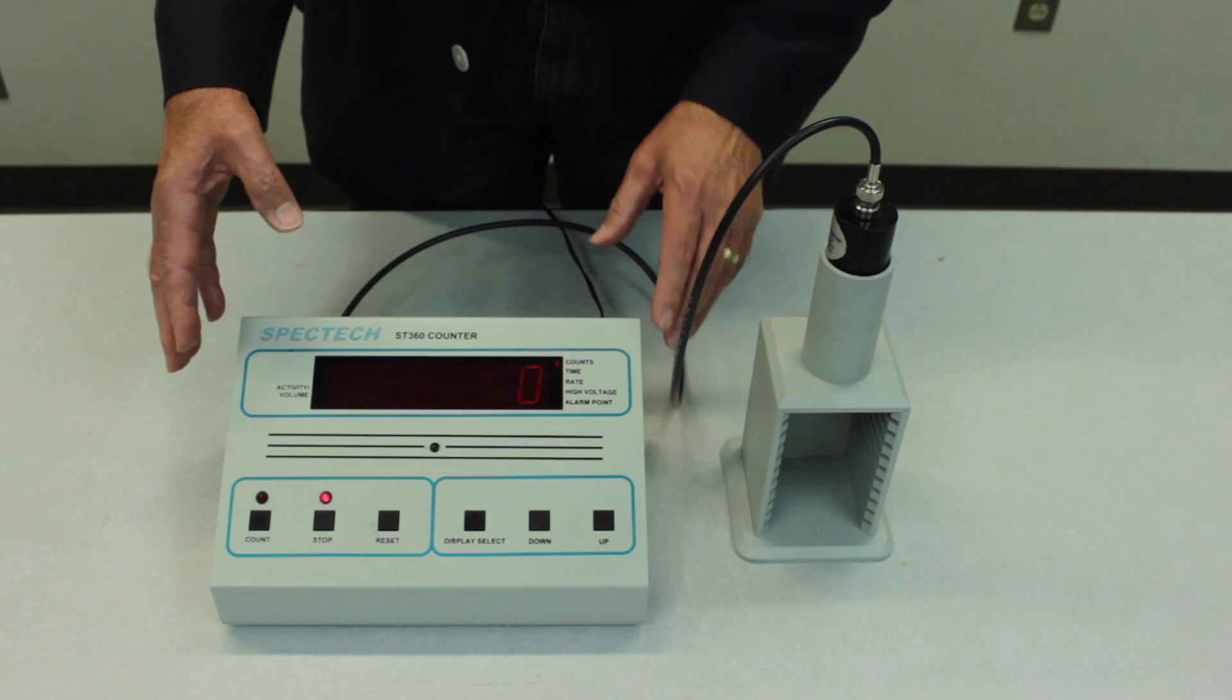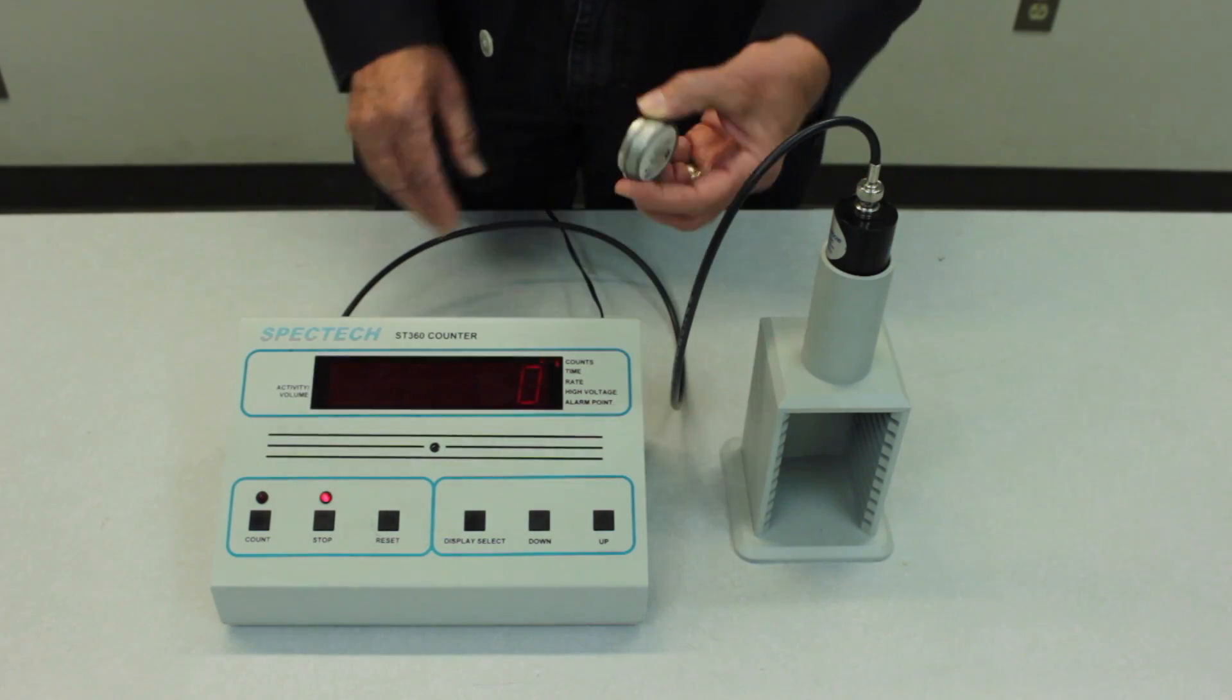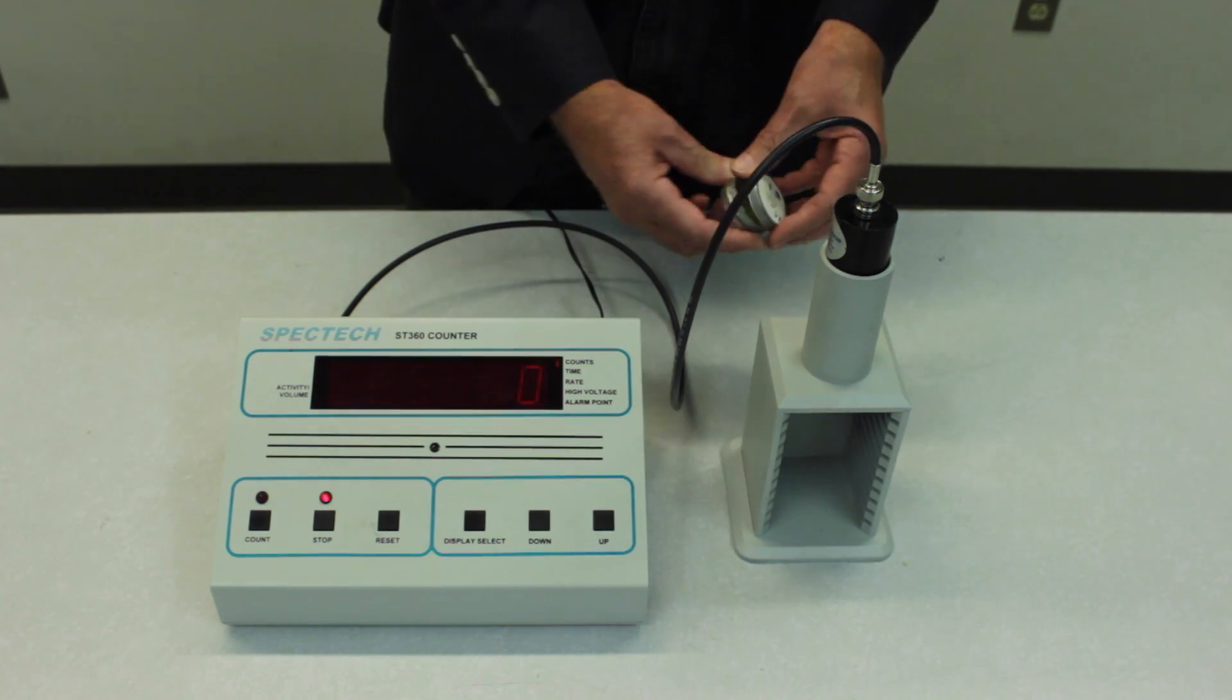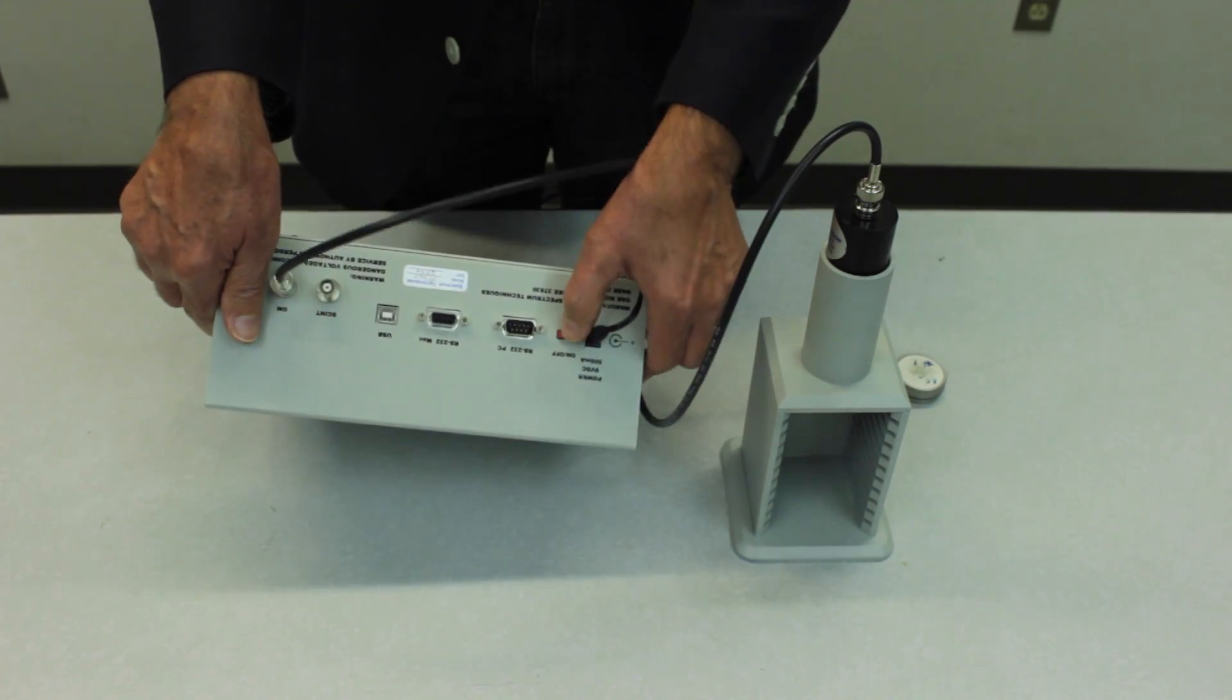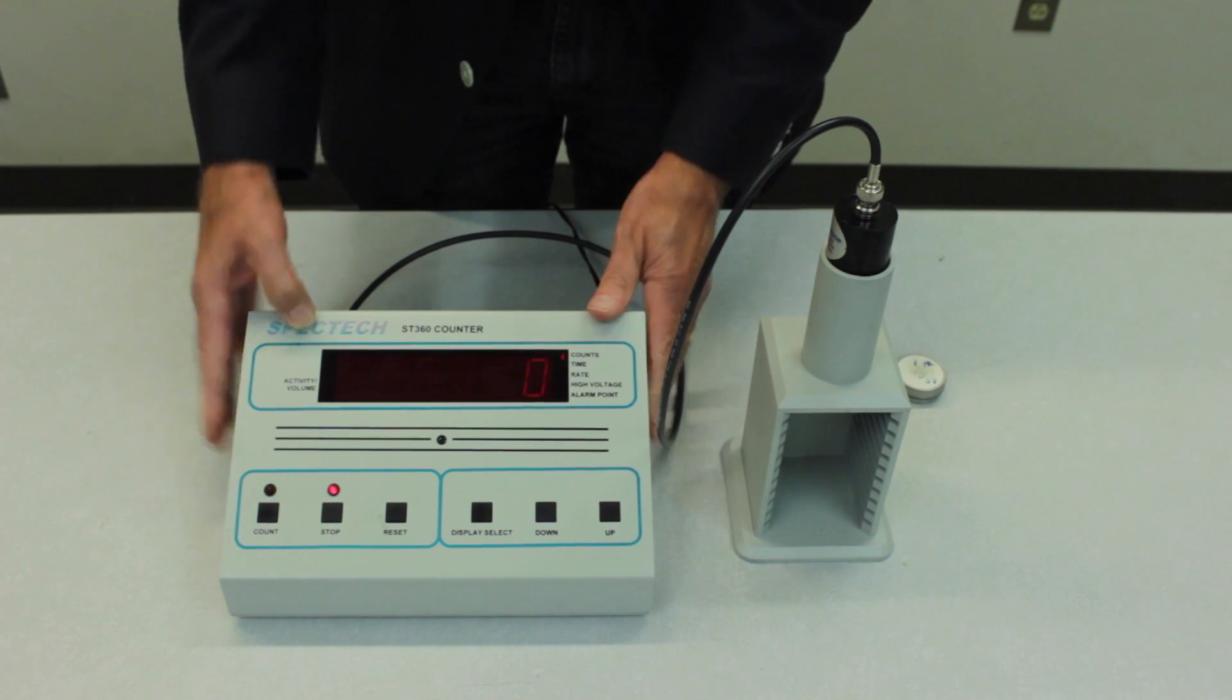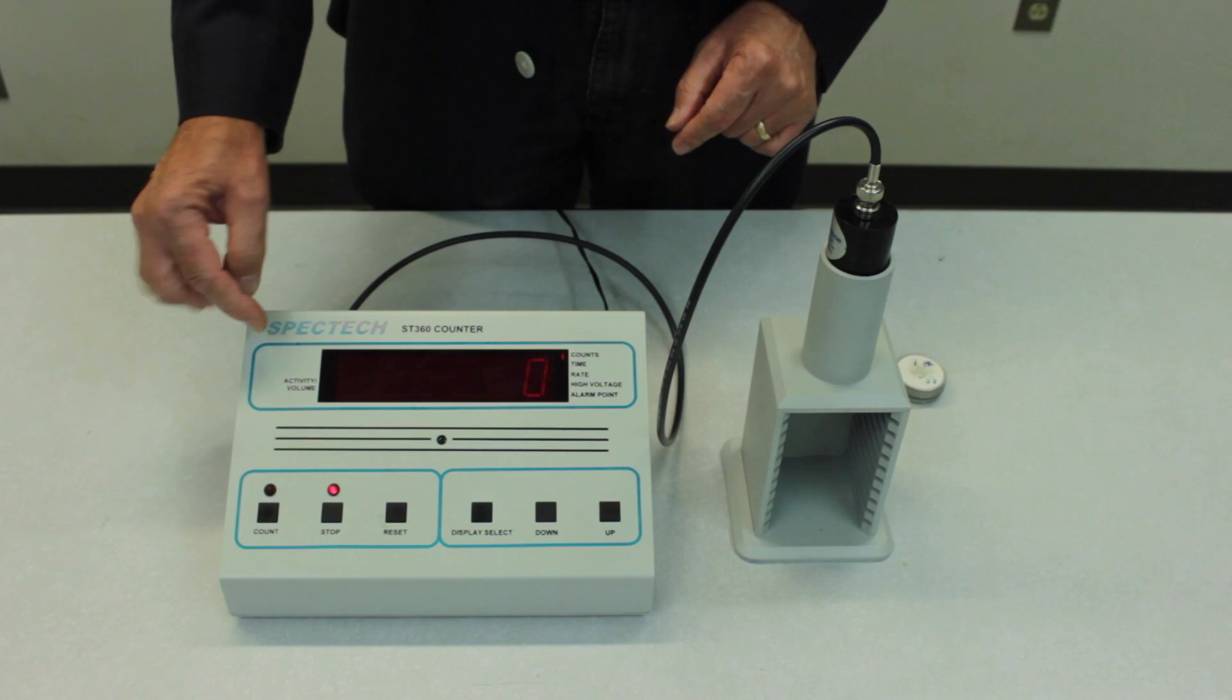In order to do the plateau curve measurement all you need is the Geiger counter apparatus and a source of radioactive material. So the instrument turns on by the power switch in the back. You just press the red button to turn it on. Then what you'll need to do is to set the counting interval and the high voltage.